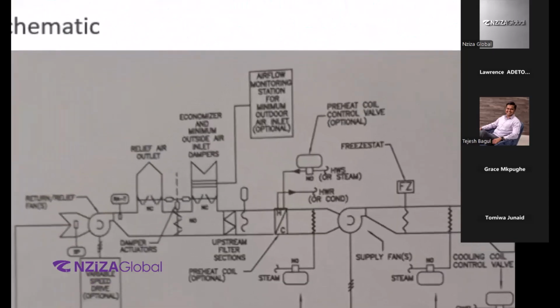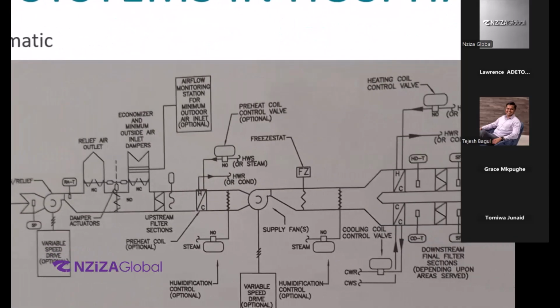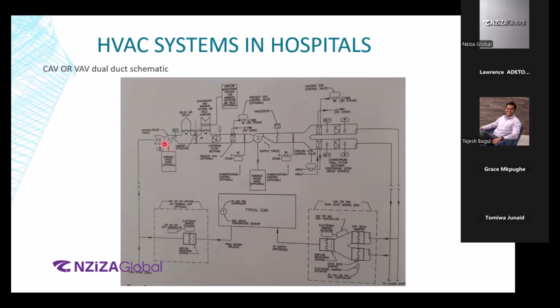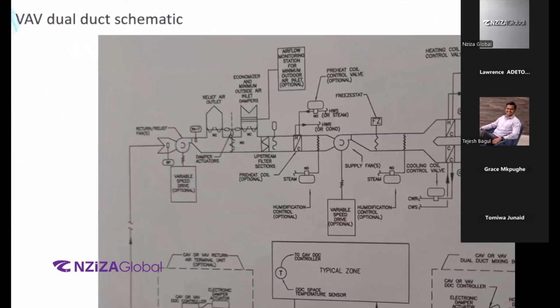space. All right. So just as we have seen earlier, we have the return air plenum over here. Now we are talking about CAV, constant air volume, or variable air volume dual duct. Okay, it stays the same. Just the introduction of a variable frequency drive or variable speed drive gets introduced when we are talking about VAV, right?